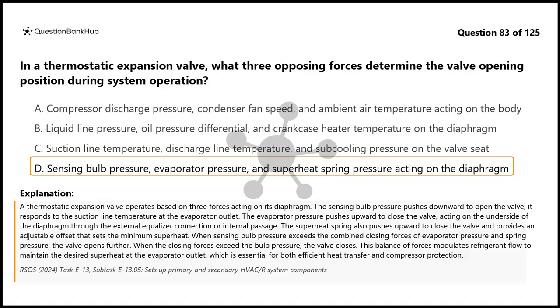connection or internal passage. The superheat spring also pushes upward to close the valve and provides an adjustable offset that sets the minimum superheat. When sensing bulb pressure exceeds the combined closing forces of evaporator pressure and spring pressure, the valve opens further. When the closing forces exceed the bulb pressure, the valve closes. This balance of forces modulates refrigerant flow to maintain the desired superheat at the evaporator outlet, which is essential for both efficient heat transfer and compressor protection.